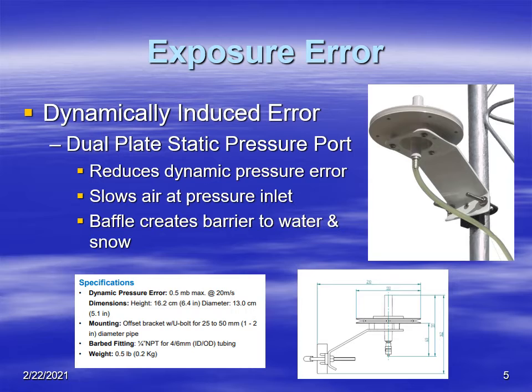There are many manufacturers of these static ports. Here's an example in this picture — it shows a two-plate static pressure port. The plate design is such that it reduces the elements: precipitation, dust, bugs, and other things from getting in the port. And it also reduces and distributes the airflow so that there is a minimal increase in pressure because of dynamic effects.